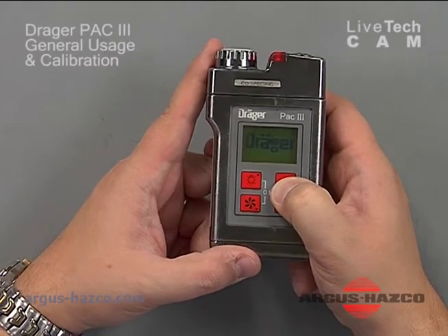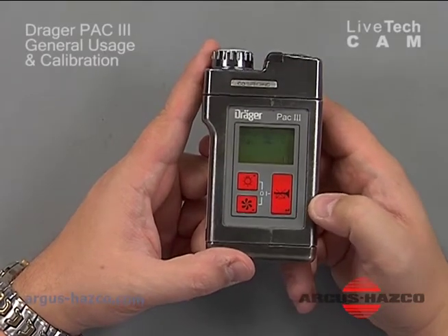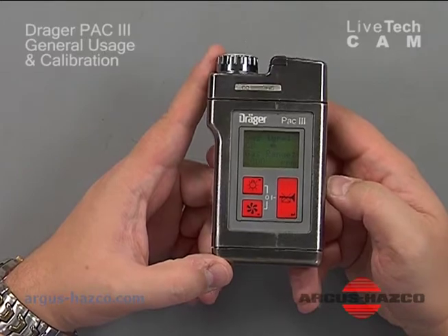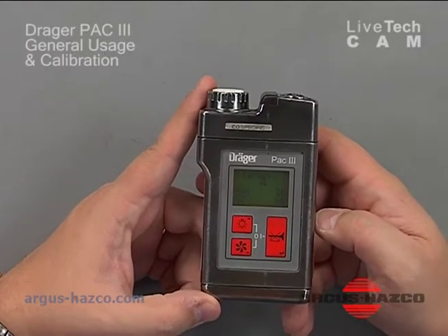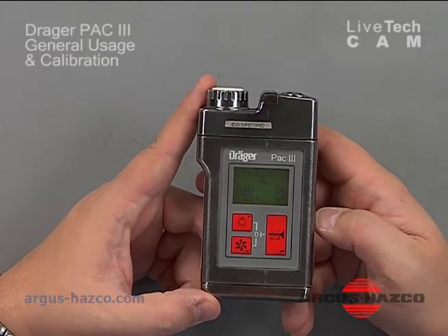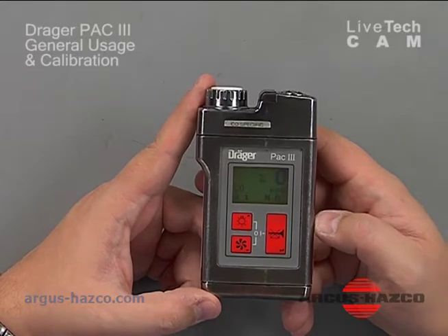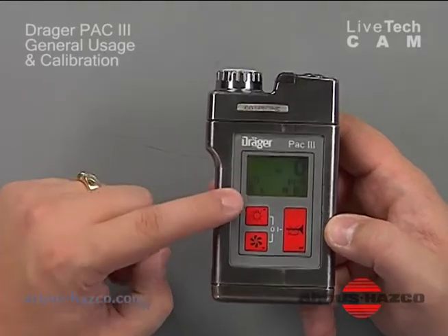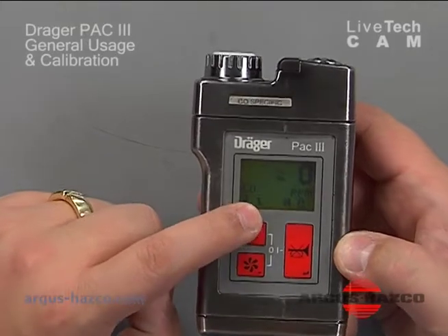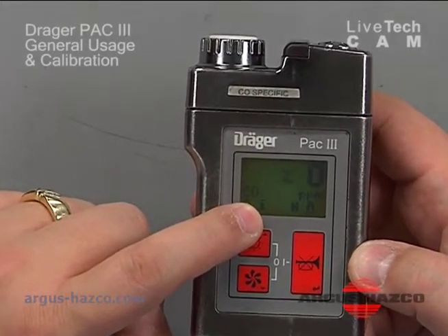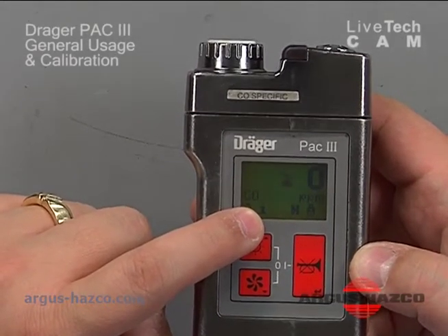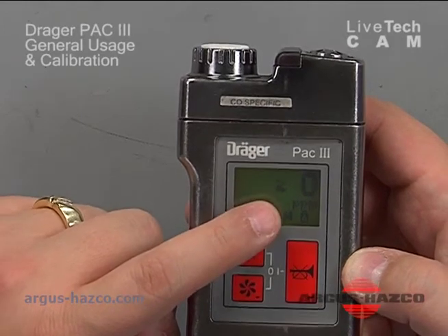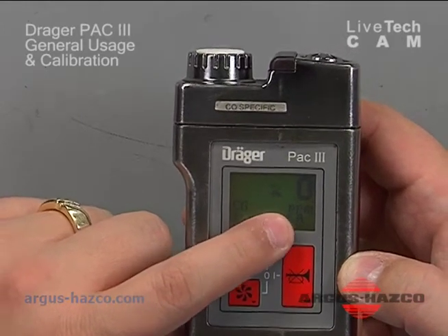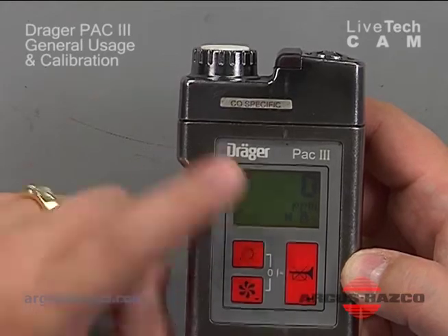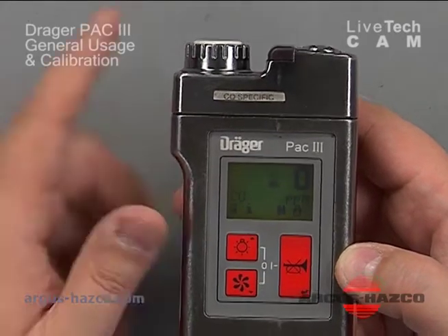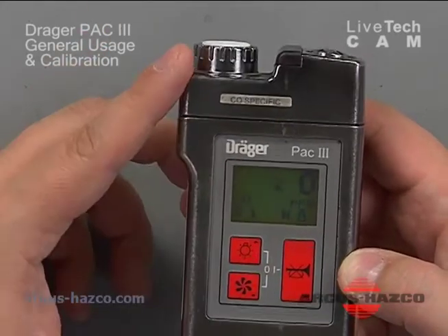Press and hold it, and you'll see Draeger come on the display, and it's going to cycle through the display, telling you it's a CO. What the range is, the TWA, the STEL, alarm 1, alarm 2, and it'll come on with a screen. And down here, this is a battery low indicator. This here tells you that you have informational warnings that you need to look at. Something's happened, so it'll tell you what's happened. The data logger is enabled, and the TWA and STEL is enabled, is what the H means.